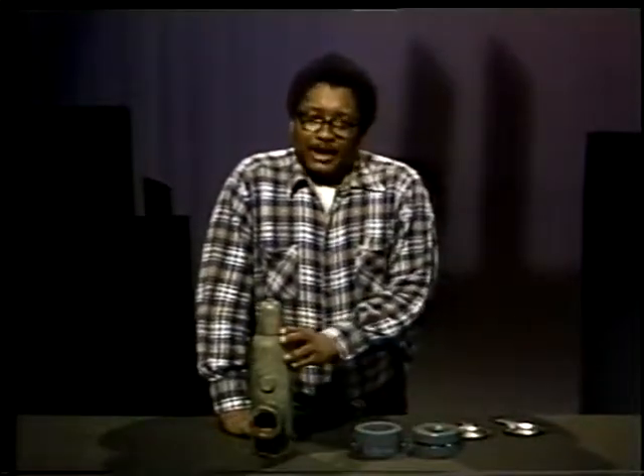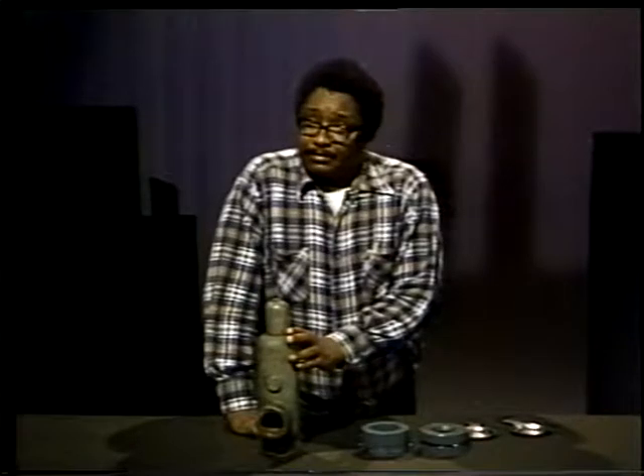This pressure relief device meets both requirements. It closes after relieving excess pressure, and it can be adjusted as necessary to maintain a very accurate set point. It's called a relief valve, and it's used primarily on systems that handle pressurized liquids. To understand how a typical relief valve works, let's start with its basic parts. The outer shell is called the valve body or valve casing. It gives overpressurized liquids a path to flow through, as well as holding the internal parts of the valve in their proper position.